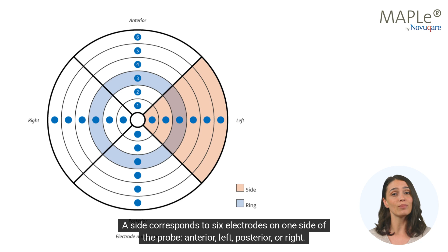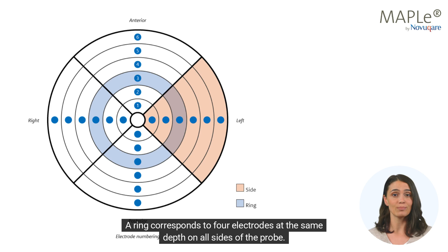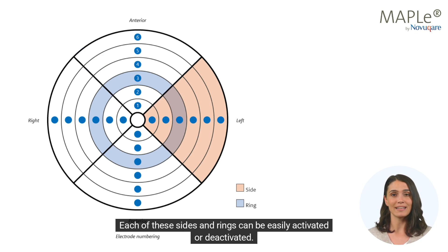The probe consists of 4 sides and 6 rings. A side corresponds to 6 electrodes on one side of the probe: anterior, left, posterior, or right. For example, the highlighted side is called the left side. A ring corresponds to 4 electrodes at the same depth on all sides of the probe. For example, the highlighted ring is called ring 3. Each of these sides and rings can be easily activated or deactivated.